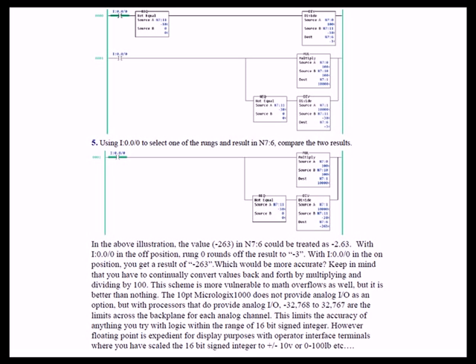Now an example here on the screen and in your manual. In N7:6, and that depends on whether input 0 is on or off. When it's off, then rung 0 executes; when it's on, then rung 1 executes. So rung 1 is true as shown here, and we ended up with a value of minus 263. However, this really would be treated as negative 2.63, because then you would have to take the result and divide by 100. But because we don't have floating point, you leave it as 263, negative 263. But keep in mind that it's really 2.63. Now if you flip the switch back off, then rung 0 rounds off the result to minus 3. And with input 0 in the on position, you get a result of negative 263, which would be more accurate.